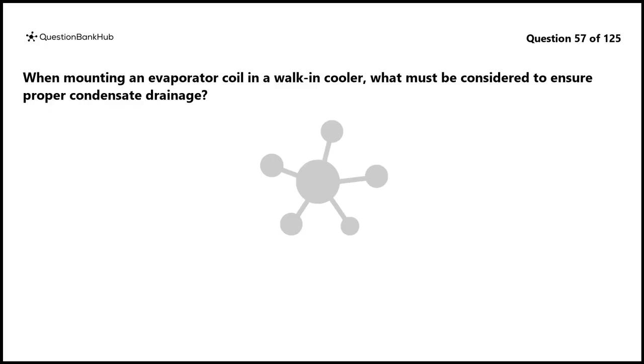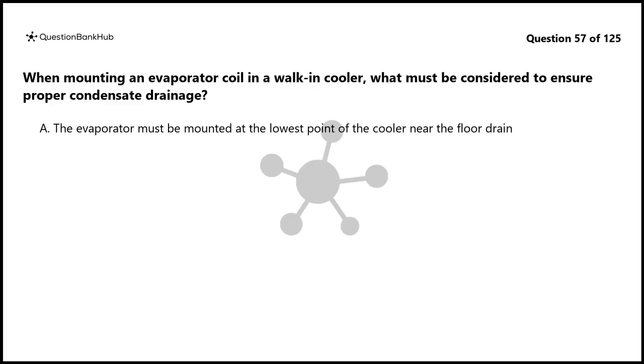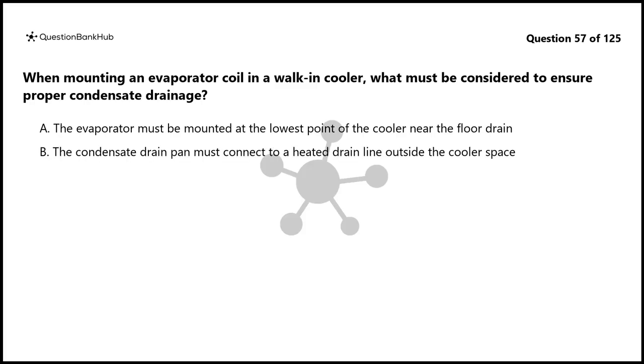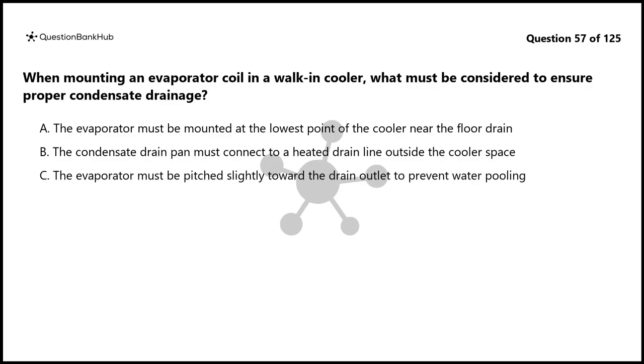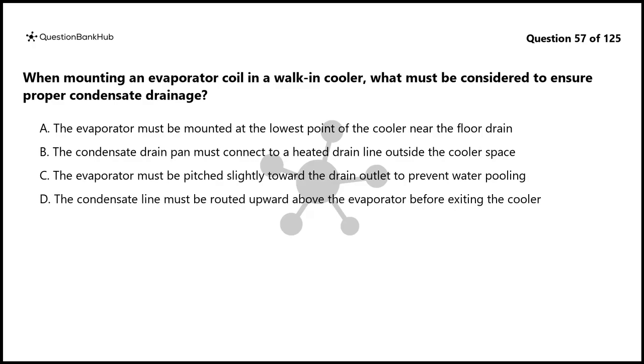Question 57. When mounting an evaporator coil in a walk-in cooler, what must be considered to ensure proper condensate drainage? A. The evaporator must be mounted at the lowest point of the cooler near the floor drain. B. The condensate drain pan must connect to a heated drain line outside the cooler space. C. The evaporator must be pitched slightly toward the drain outlet to prevent water pooling. D. The condensate line must be routed upward above the evaporator before exiting the cooler.